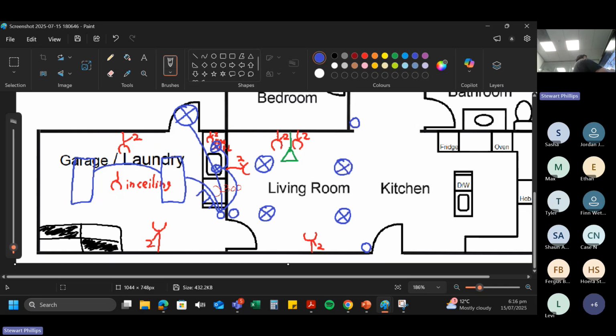Cool. And then we've got to pick what's going to be our intermediate switch. So thinking about where our switchboard is, we're probably going to have the feed here. So this is going to be a 2-way switch. Then the next closest switch is here. And this is what an intermediate switch looks like. Kind of looks like some kind of spider crab thing. And then we're going to have another 2-way switch over here.